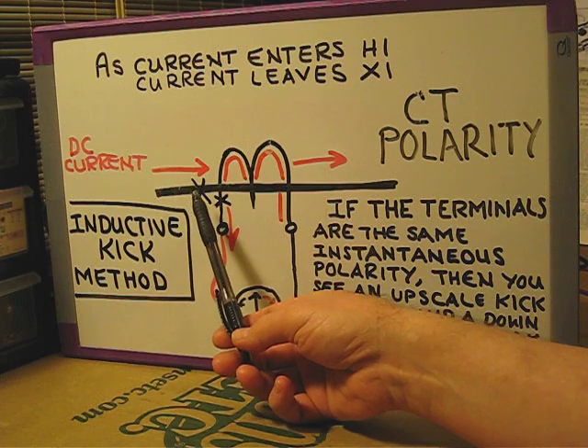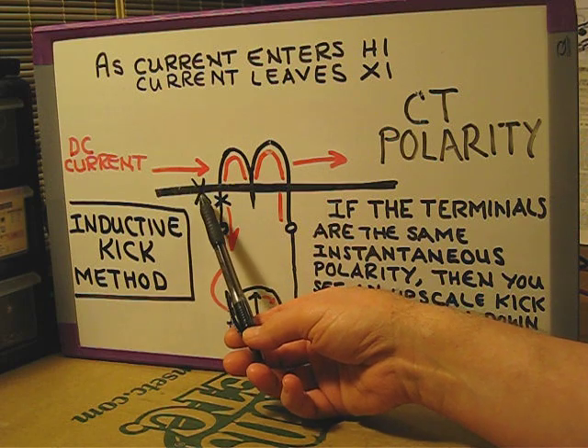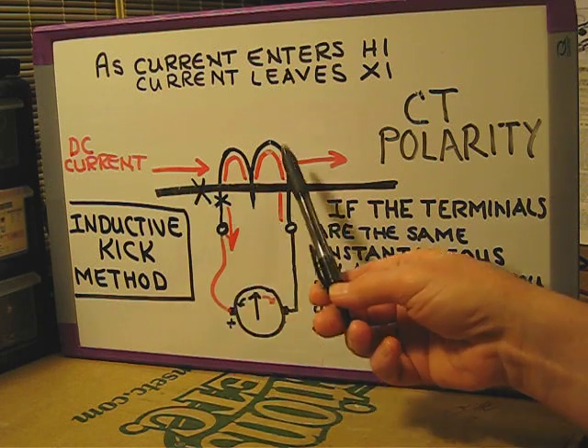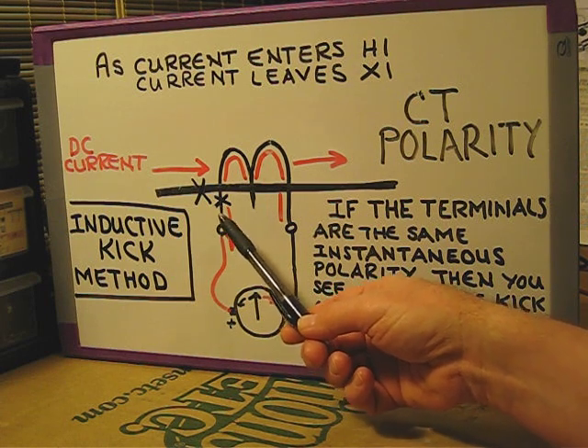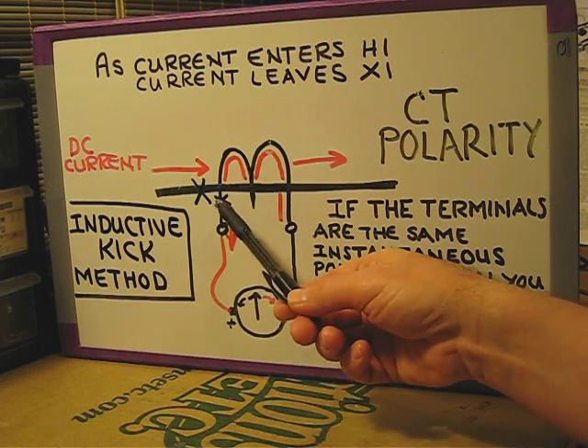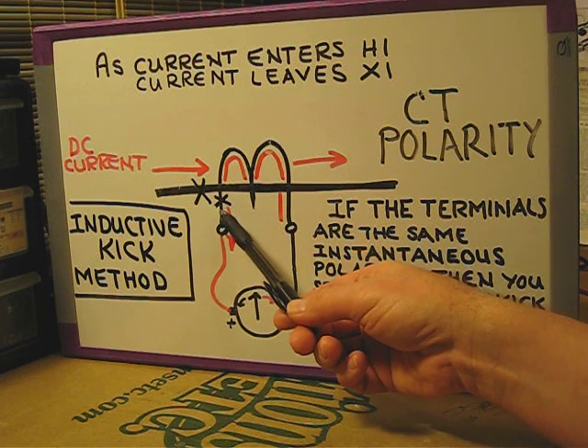We'll inject a positive DC current into the H1 side of our CT. As H1 becomes positive and the current enters H1, current will leave the X1 terminal.